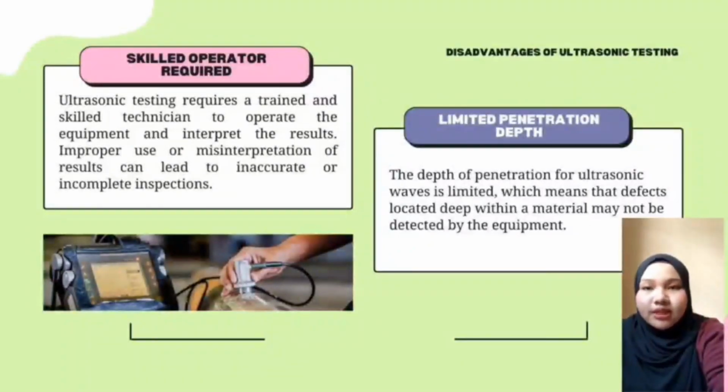The transducers alert to both the normal structure of some materials, tolerable anomalies, and other specimens, and to faults therein severe enough to compromise specimen integrity. These signals must be distinguished by a skilled technician, possibly requiring a follow-up with other non-destructive testing methods.